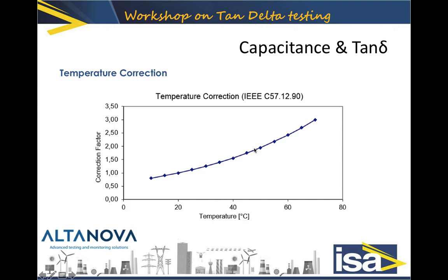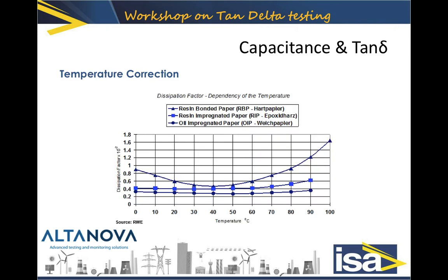When talking about bushings, there are three major types: resin bonded paper (RBP), resin impregnated paper (RIP), and oil impregnated paper (OIP). The temperature correction for bushings looks a little different for each type, as shown on this table.